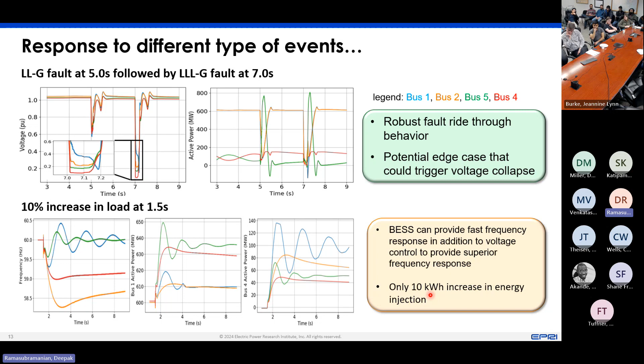So let's actually see if it works on a real network. So we did a study looking at the application of it in South Texas. What happened in South Texas was that they had a stability criterion wherein they could not increase the inverter-based resource percentage beyond 70% in that region. So the green curve at the back here is a stable response for a fault when the level of wind was 70%. Of course, it's a curtailed value, right? So if you have a 100 megawatt plant, it is curtailed down to 70 megawatt so that it is able to provide a stable response. And if that 100 megawatt plant went up to 99 megawatts, to try to utilize its entire capability, then there were oscillations introduced, shown by this blue curve.